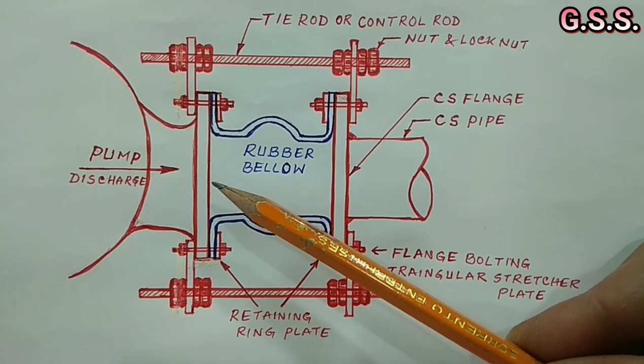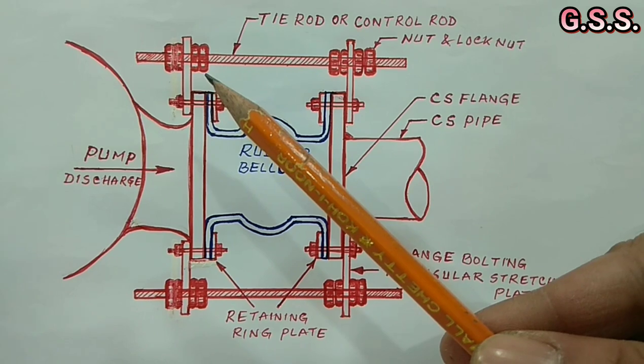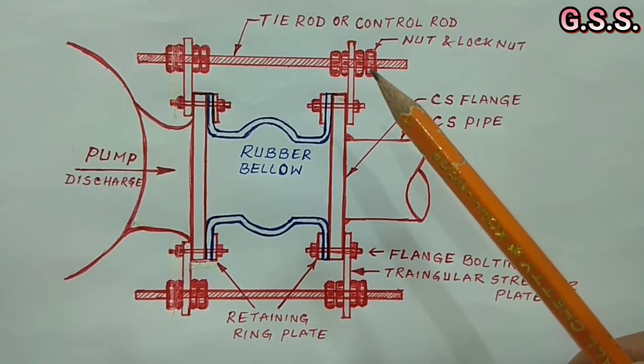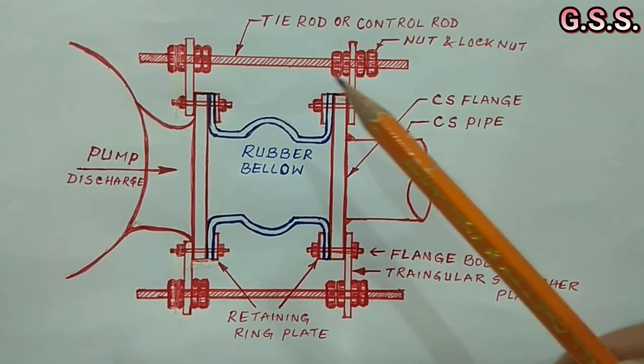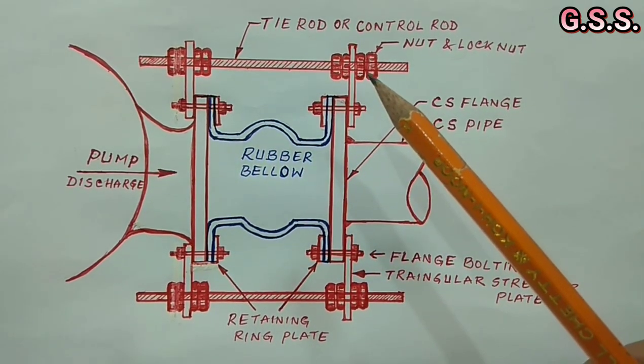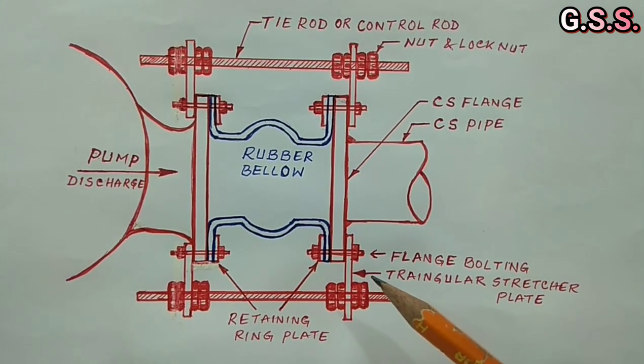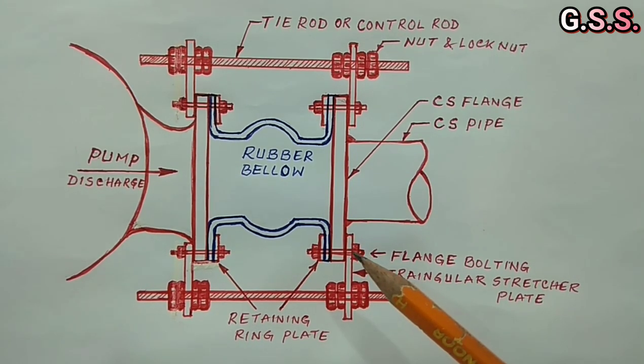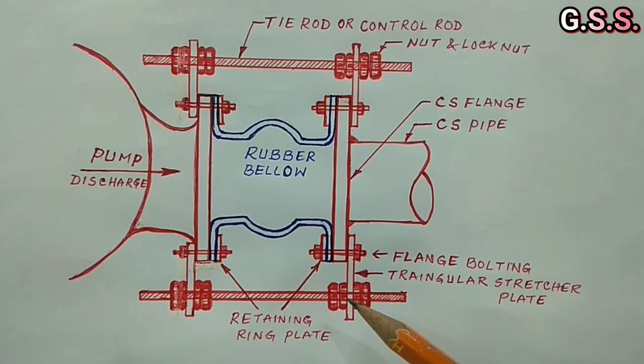Now, we have to tie tie rod nuts with lock nuts on both sides of the bellow. There are total eight number of nuts, four nuts and four lock nuts. Tie rod is connected with the flange with triangular stretcher plate having three holes: two holes passes through flange bolting and one hole for the tie rod.